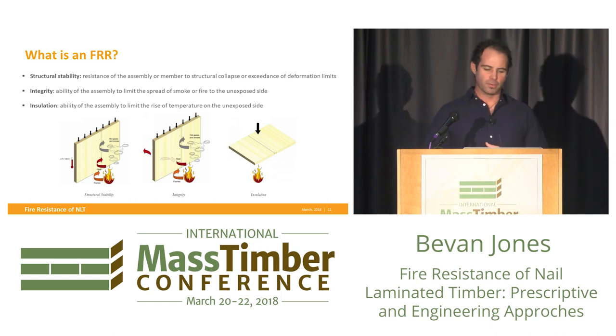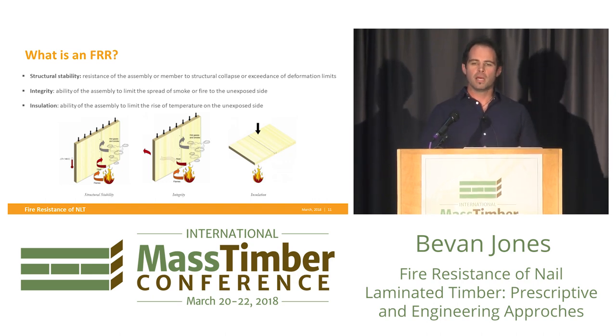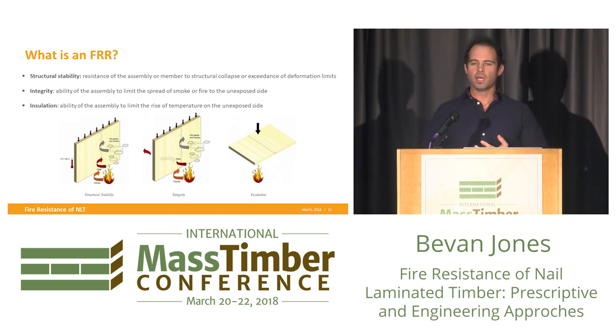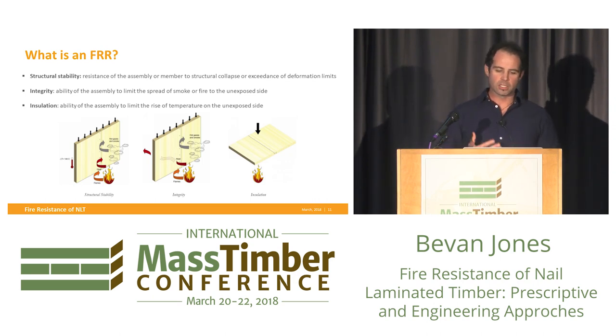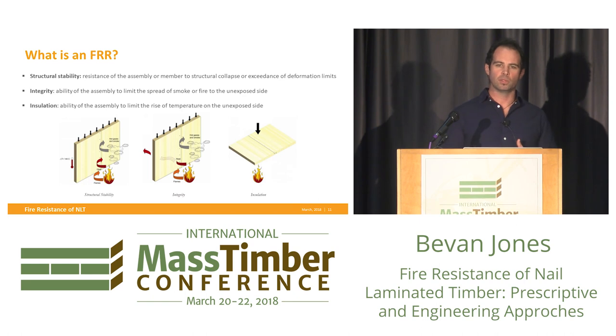What is a fire resistance rating? It's made up of three parts for a load-bearing assembly: structural stability — the assembly must sustain its load carrying capability for the duration of fire exposure; integrity — it must prevent the passage of flame and hot gases through the assembly; and insulation — it must resist temperature rise so that temperatures on the unexposed face don't get excessive. Non-load-bearing assemblies essentially require only the integrity and insulation components.